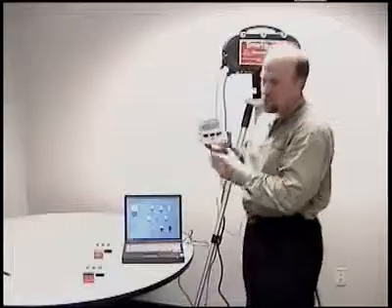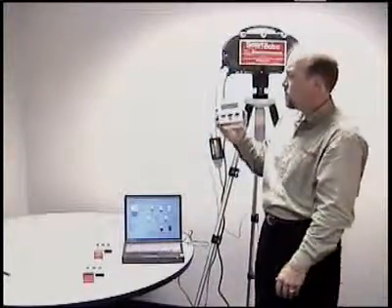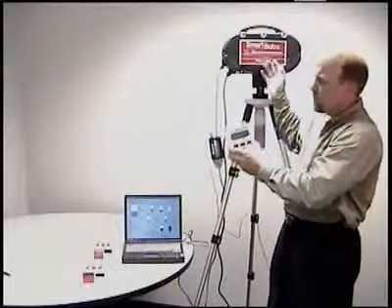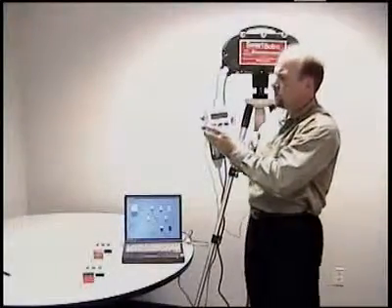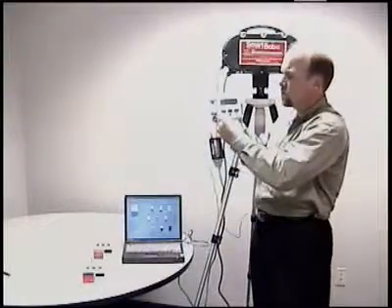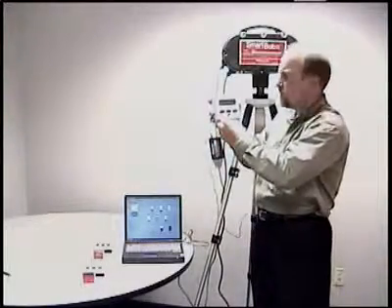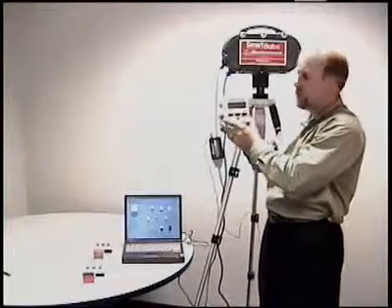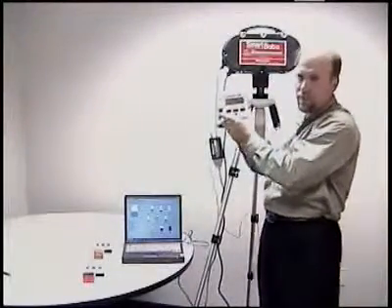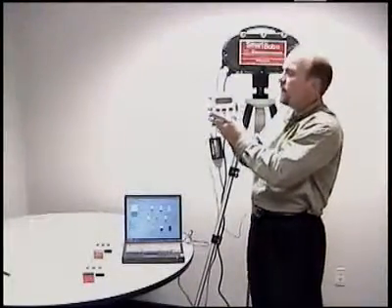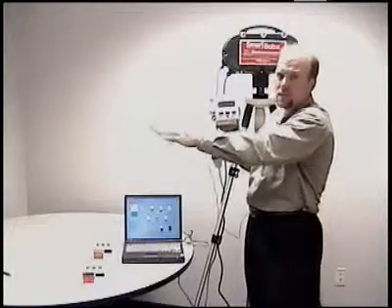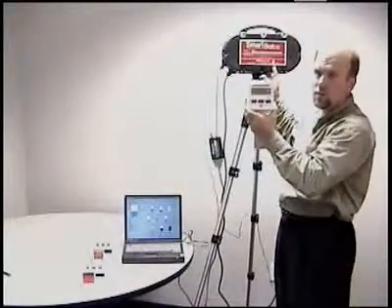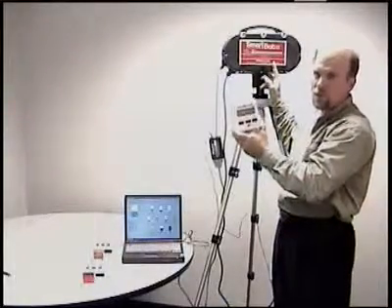We have an RSU, which is a remote start unit, the interface between a PLC or DCS and the SmartBOB2 remote. You get a dry contact closure in from the PLC or DCS to initiate the measurement. Digital information is sent back to the RSU, and an analog 4 to 20 milliamps signal is then sent back to the PLC. Each SmartBOB2 remote will require a remote start unit.